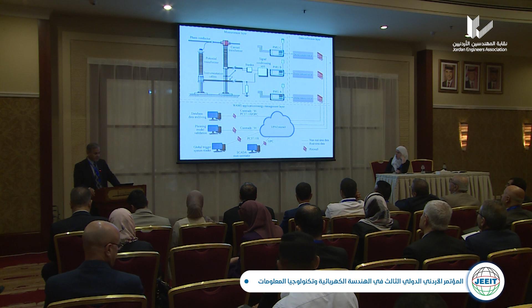This figure shows three layers. The measurement layer, where we have three PMUs, A, B, and C, connected to the power system through the CT and VT. Then reporting the data with high sampling rate through any communication channel, through internet. Then these data could be used for different applications, and we have two kinds of application: that which requires non-real time, like data archiving or for planning, and some applications need real-time data, like the state estimator and global trigger system.